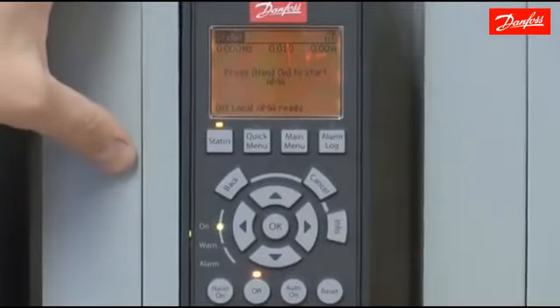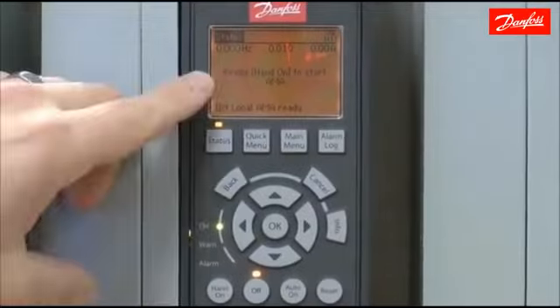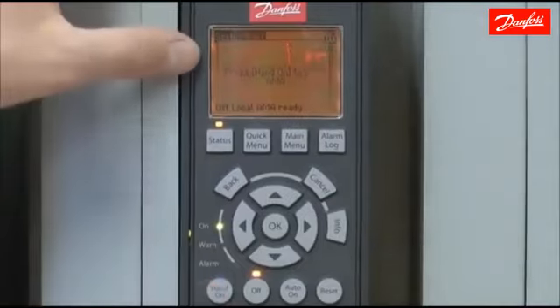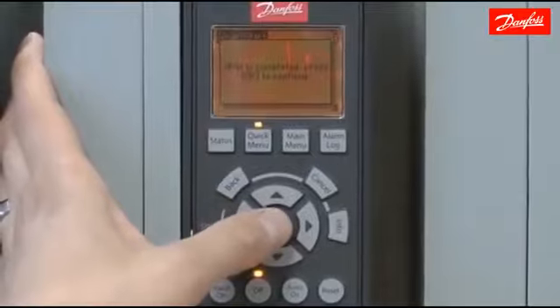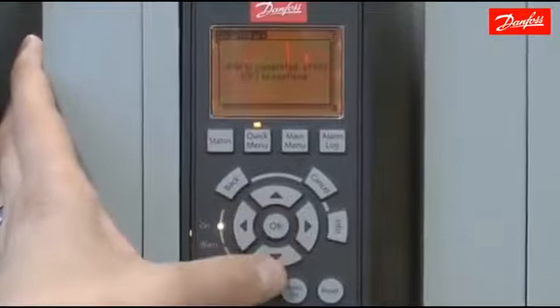Press hand on to start. This procedure can take anywhere from 1 to 10 minutes depending on the motor size. So I'm going to press hand on to start the AMA. Once the AMA procedure is complete, you'll see this screen. It's telling me to press OK to continue and accept the values that the motor tuning has learned.